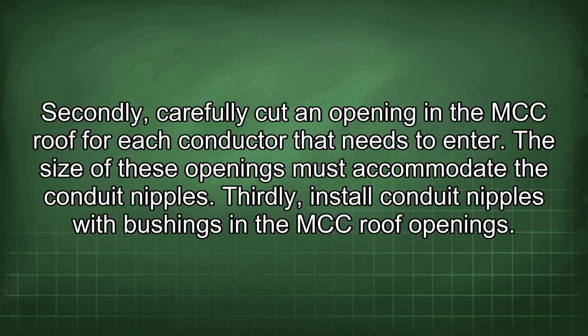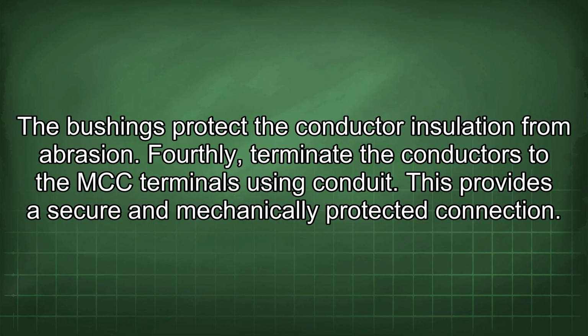Thirdly, install conduit nipples with bushings in the MCC roof openings. The bushings protect the conductor insulation from abrasion. Fourthly, terminate the conductors to the MCC terminals using conduit. This provides a secure and mechanically protected connection.